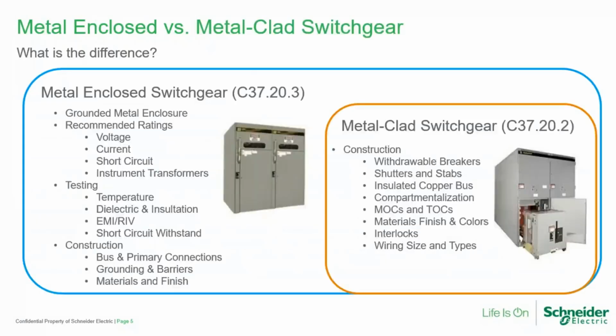So one question I often get, and which is not necessarily easily understood, is what's the difference between metal enclosed switchgear and metal clad switchgear, and why would I, as a switchgear manufacturer, rate one type of my switchgear according to one versus the other? I often like to think about this in terms of the fingers and thumbs analogy. All thumbs are fingers, but not all fingers are thumbs. All metal clad switchgear, which is the withdrawable style circuit breaker switchgear, is a type of metal enclosed switchgear, but not all metal enclosed switchgear is metal clad switchgear. I think that's the easiest way to think about it.